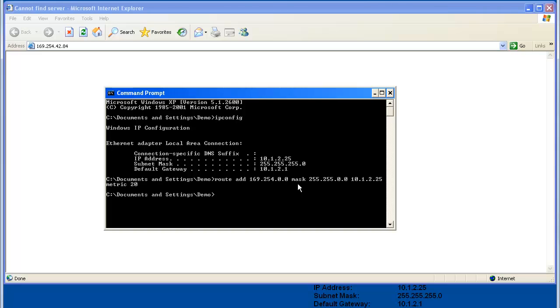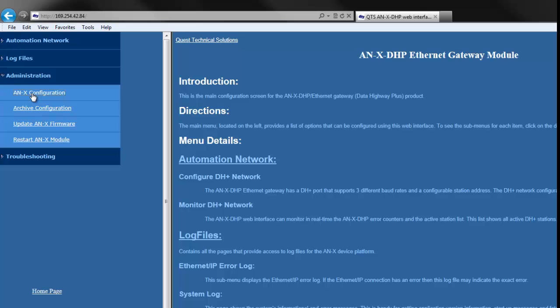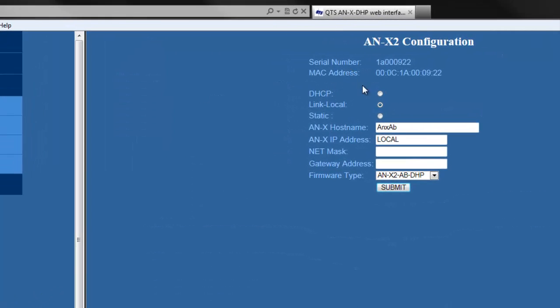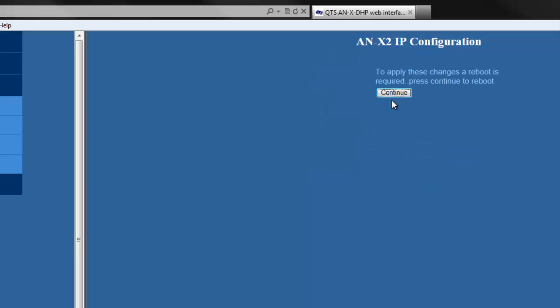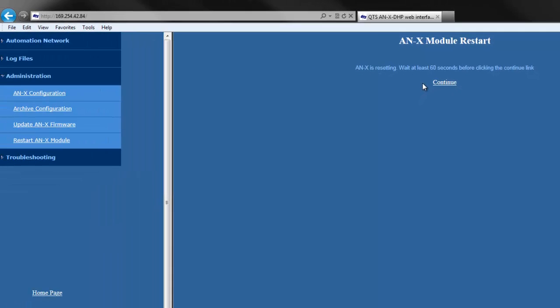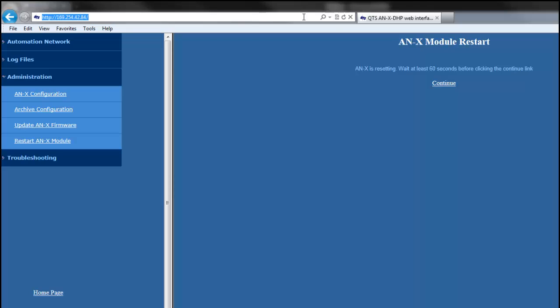If everything was entered correctly, you should be able to access the ANX2's web page now. We're going to type in the default IP address and choose an ANX2 configuration. I'll change the module to static IP address and name it ANX2 AB-HMI. Then I'll set the IP address, the net mask, and the gateway. We'll choose the DHP firmware, and when all this is done, select Submit, then click Continue. After waiting 60 seconds, type in the IP address we just assigned the module, which is 10.1.2.14, and that should take you to the module's configuration page.